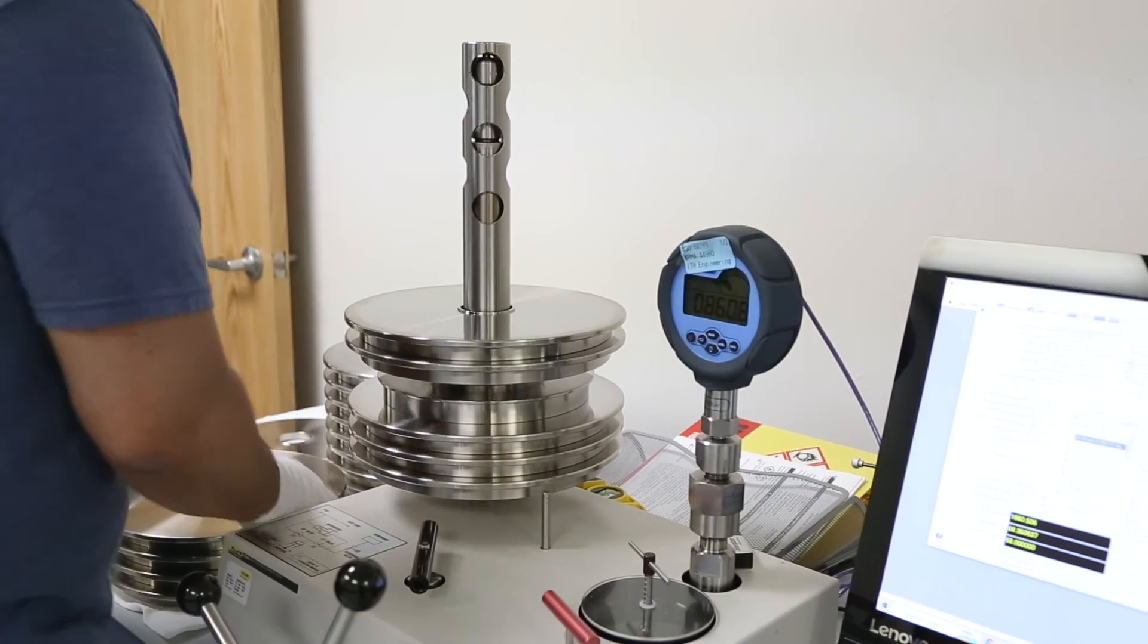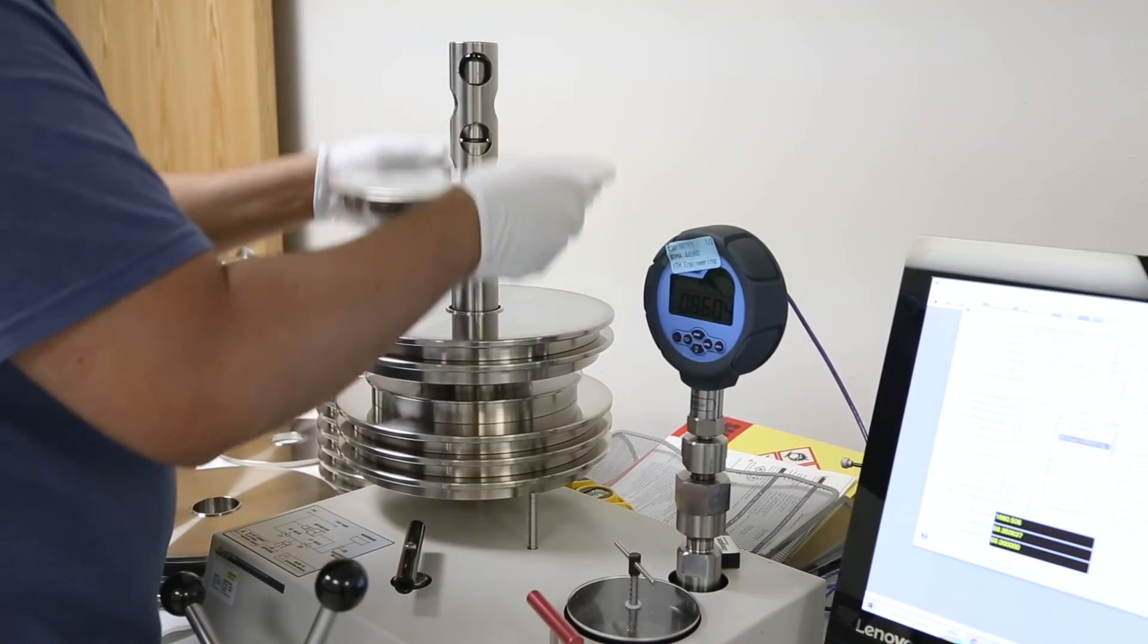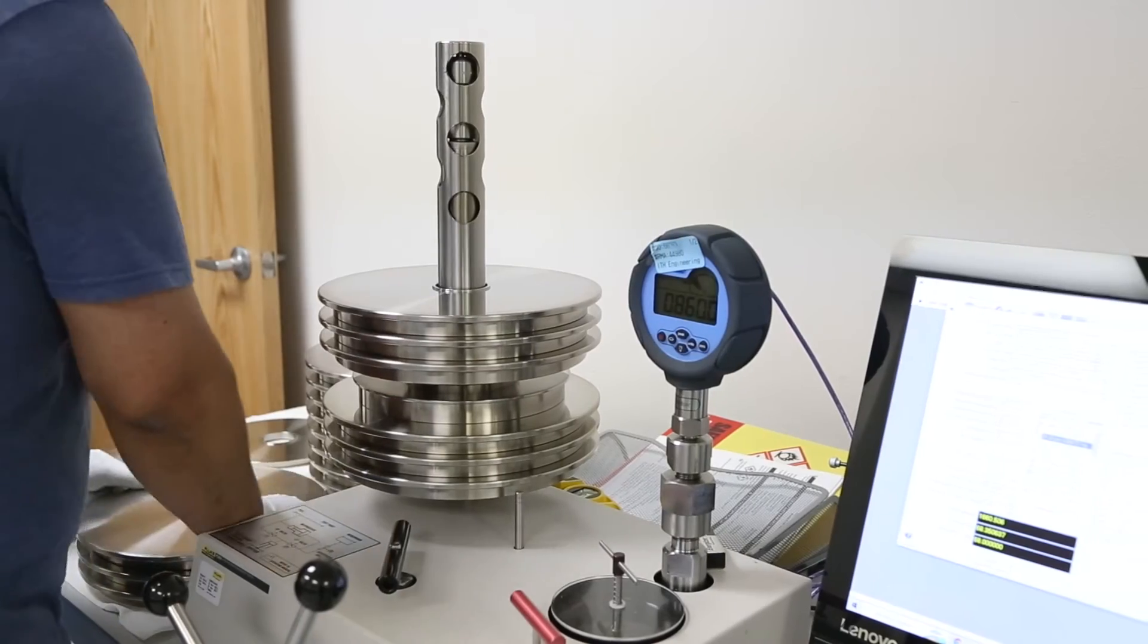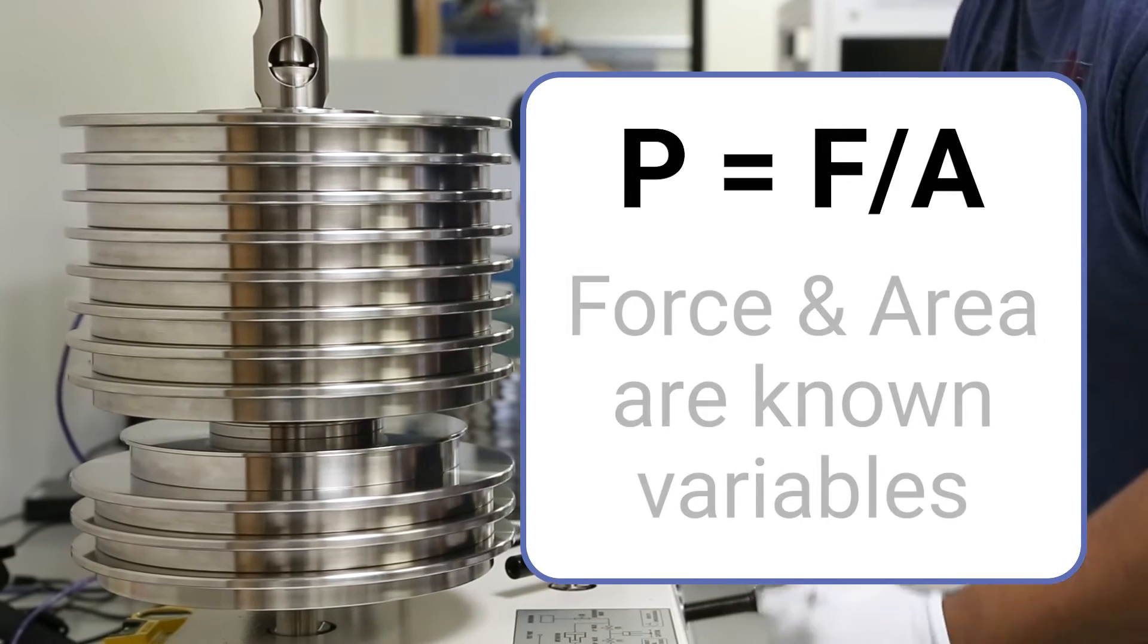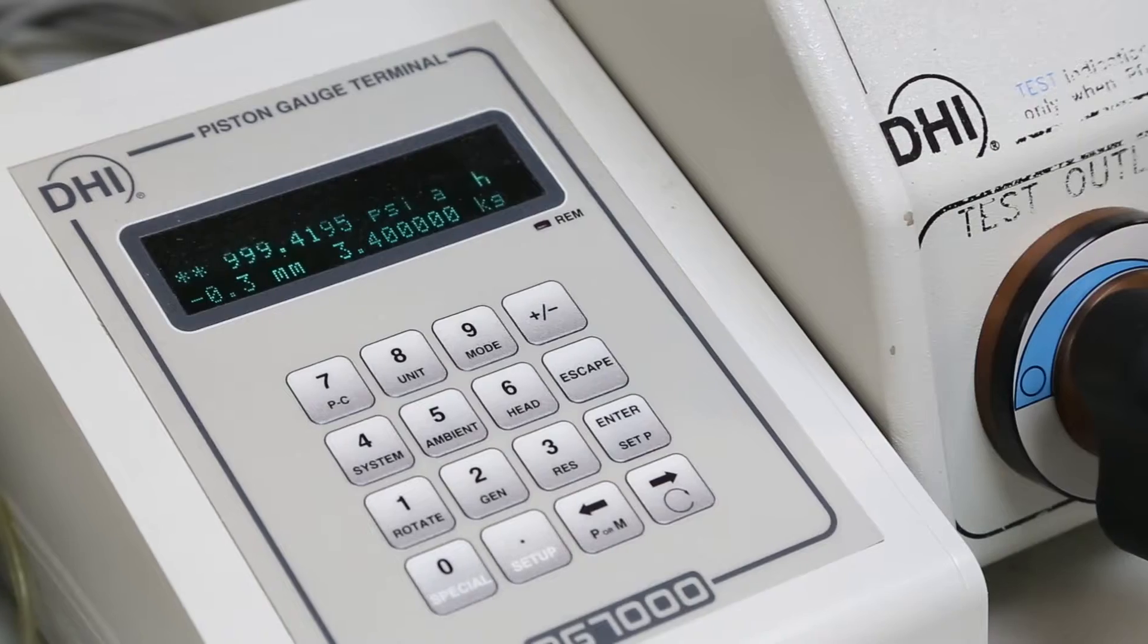A piston gauge obtains pressure by placing mass on a floating piston in a cylinder with a defined area. Since this pressure can be simplified to the equation pressure equals force over area, with known variables, deadweight testers are incredibly accurate, allowing them to function as the reference in a test.